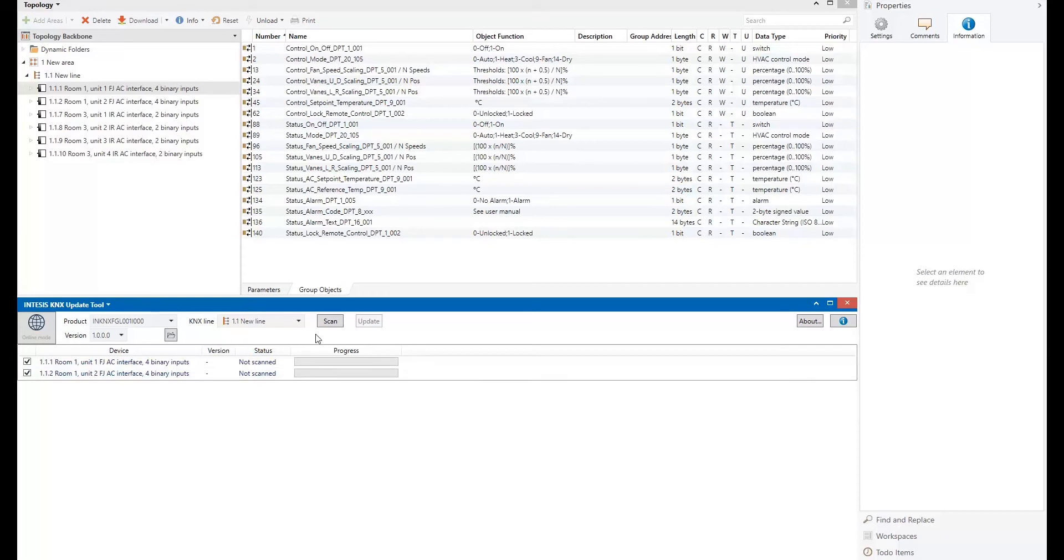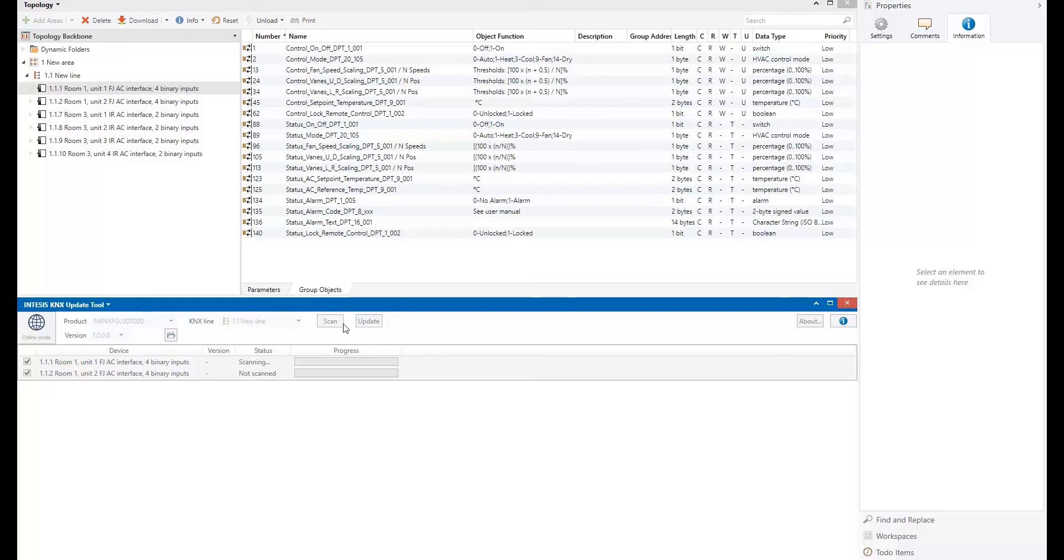But now, what we will do by pressing the scan button, the ETS app will retrieve the firmware version of the products of the devices in the installation. Basically, to know if they are in the installation and also if they are reachable from the KNX interface or KNX programmer location. Because sometimes they may not be included there.